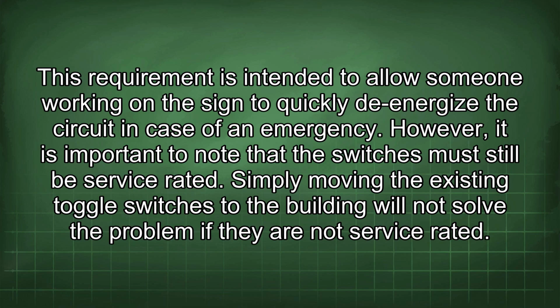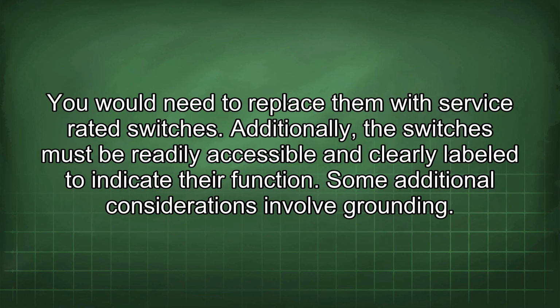However, it is important to note that the switches must still be service rated. Simply moving the existing toggle switches to the building will not solve the problem if they are not service rated. You would need to replace them with service rated switches. Additionally, the switches must be readily accessible and clearly labeled to indicate their function.